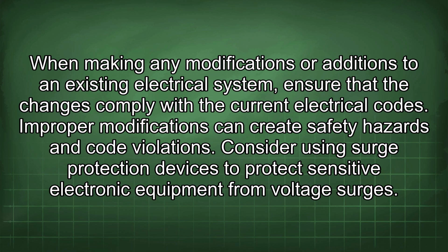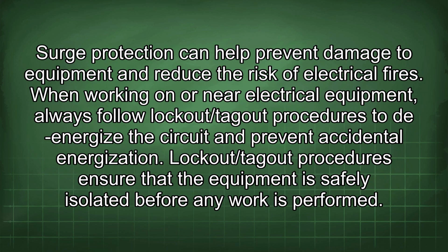Consider using surge protection devices to protect sensitive electronic equipment from voltage surges. Surge protection can help prevent damage to equipment and reduce the risk of electrical fires. When working on or near electrical equipment, always follow lockout/tagout procedures to de-energize the circuit and prevent accidental energization. Lockout/tagout procedures ensure that the equipment is safely isolated before any work is performed.